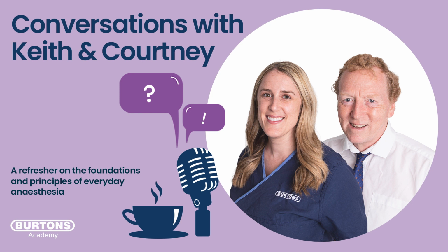So having got the right setup, we know it's working correctly. We've done our little flush test and our square wave test. We got a little 1 or 2 oscillations of bounce, and then we're back to normal. We've now got a waveform that can tell us several things, and it's a difficult medium to describe with our audio medium here. But we imagine we've got an upstroke, so this is the very rapid rise as the pressure wave goes up, rounds off at a peak, comes back down relatively slowly, and then we often get a little blip, which we call a dicrotic notch.